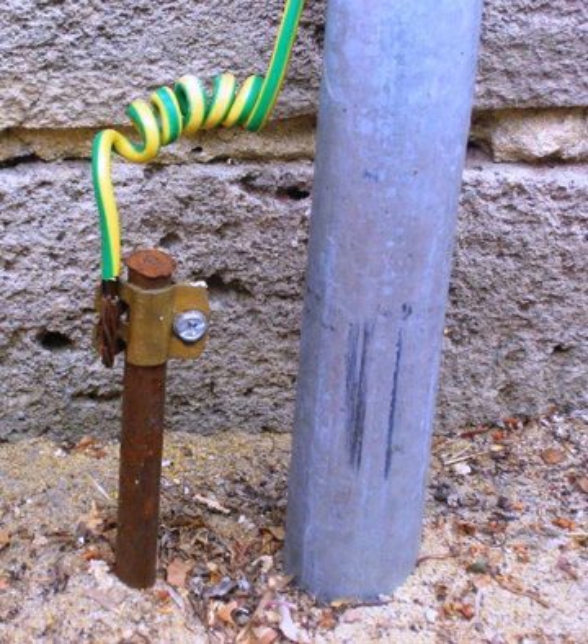A particular concern in design of electrical substations is earth potential rise. When very large fault currents are injected into the earth, the area around the point of injection may rise to a high potential with respect to distant points. This is due to the limited finite conductivity of the layers of soil in the earth.